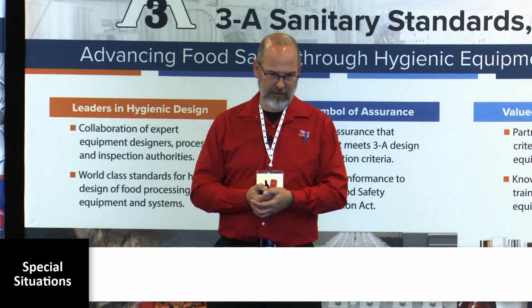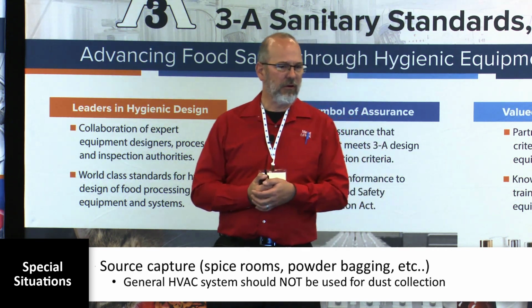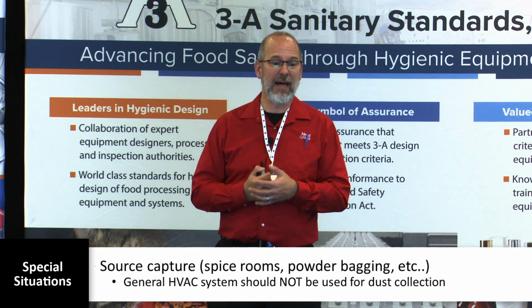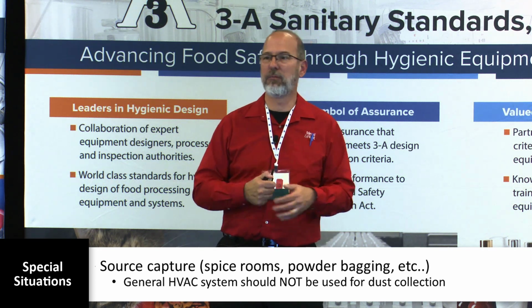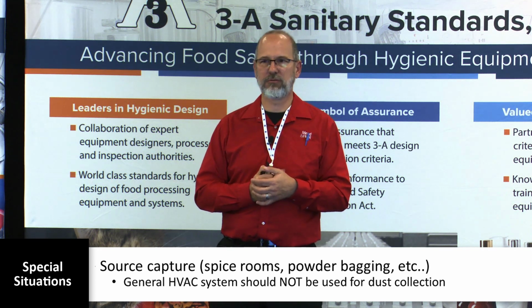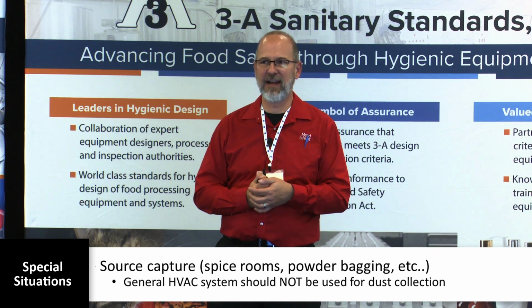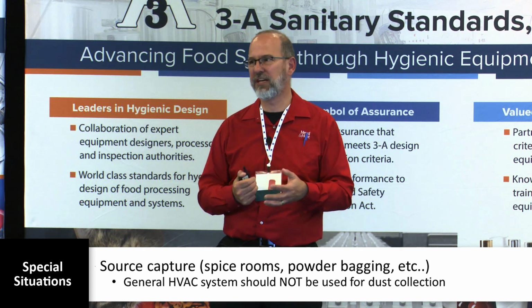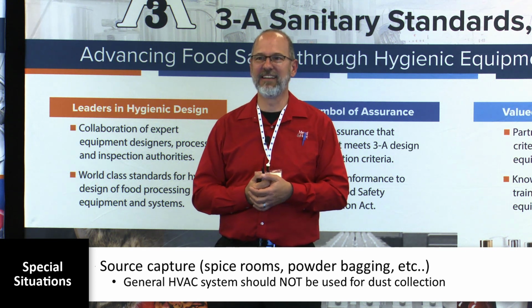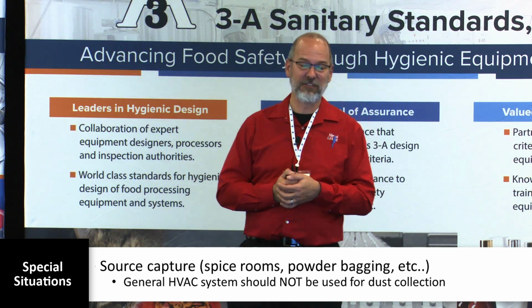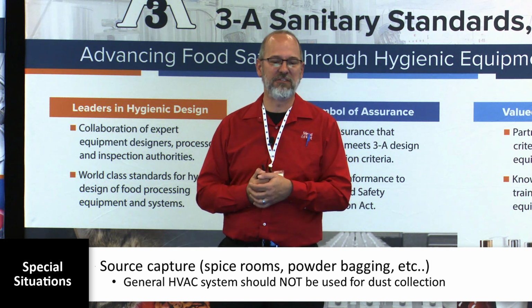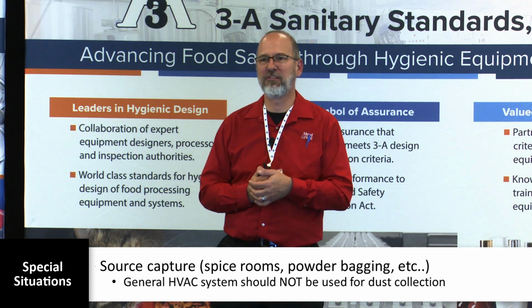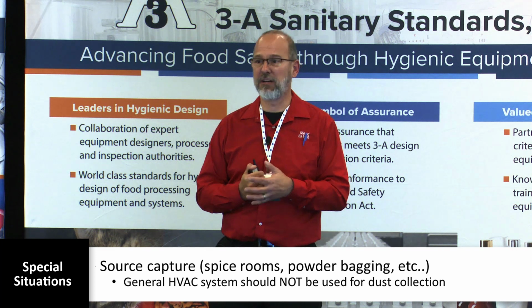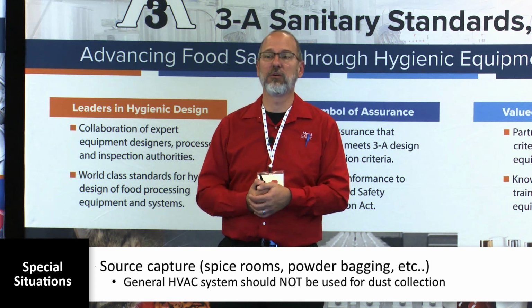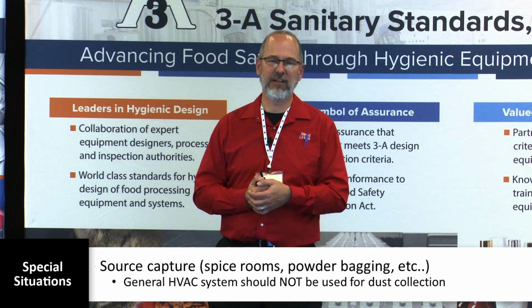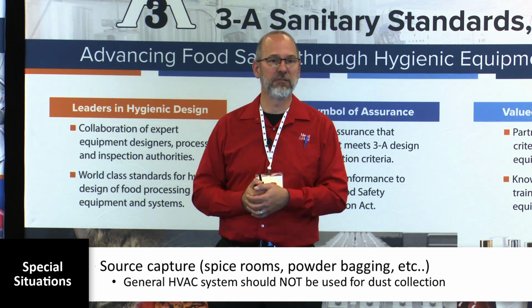If you've got a situation where your food process is generating a lot of dust, like you've got a spice storage room or powder bagging or something like that, don't treat your air handler as a dust collector. They're not really generally designed for that. You can do it, but you'll be changing out your filters every other day. Your maintenance folks won't like that at all. So if you do have special dust generating process elements, consider dust collection at source capture. Capture it at the source and dust collect it. That'll greatly extend the life of your air handler and the filters in the air handler, and you won't be cleaning it as often.